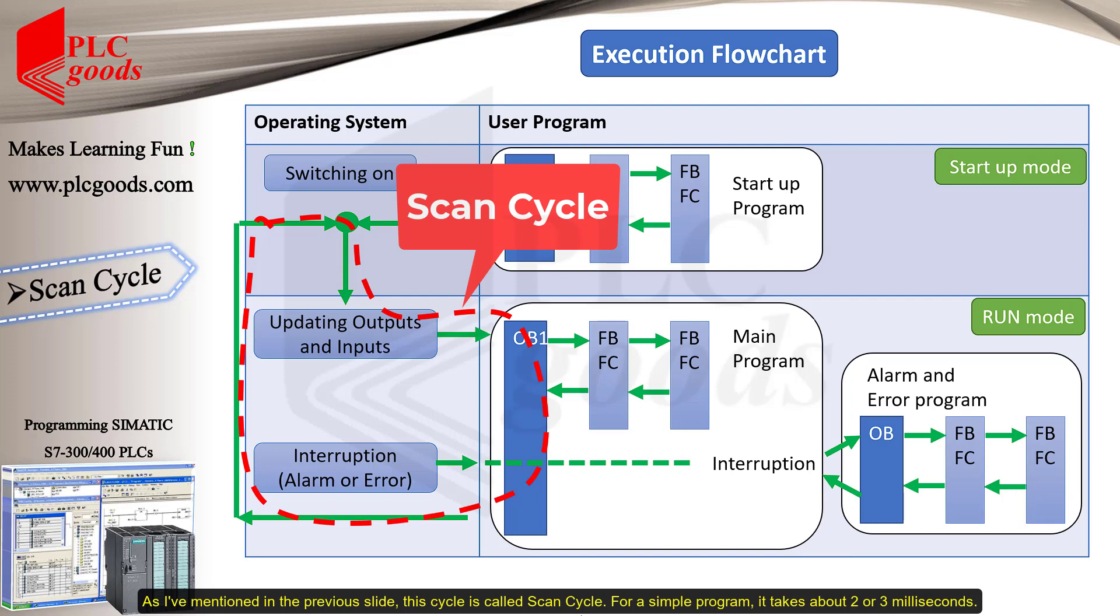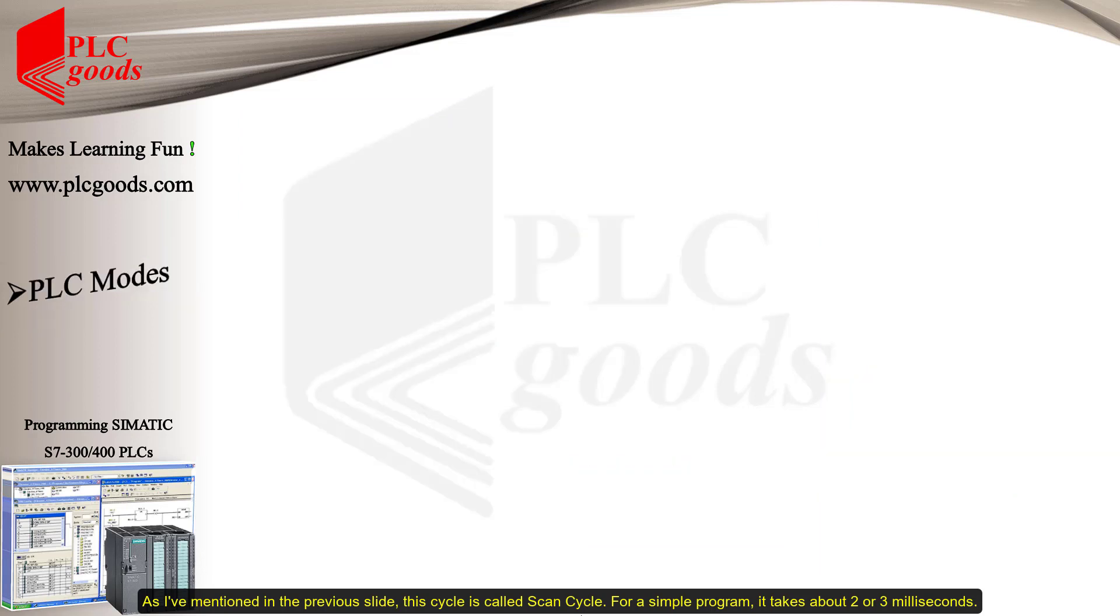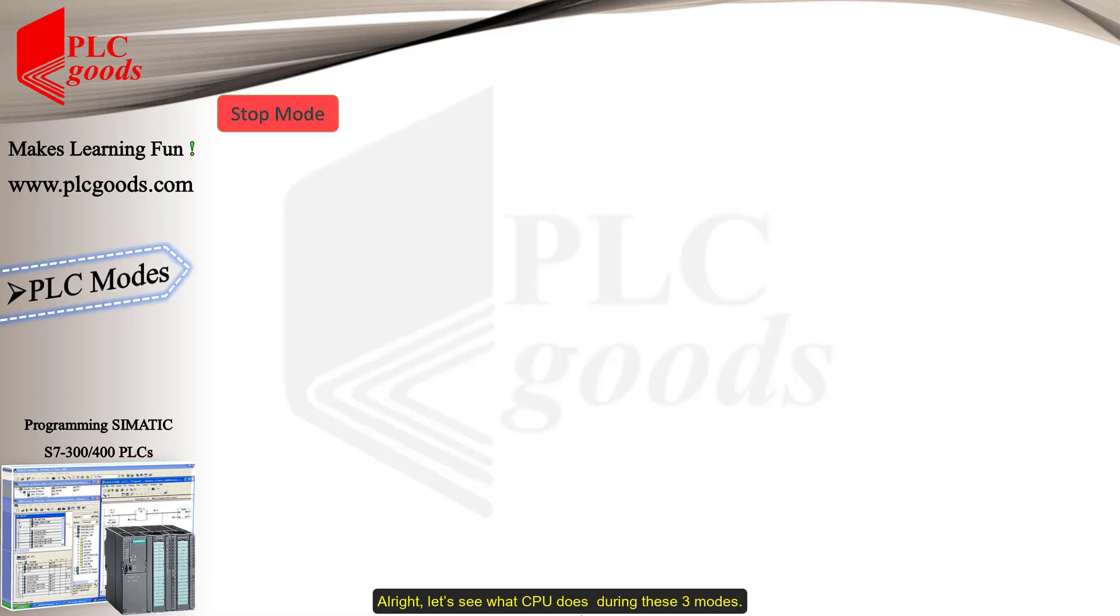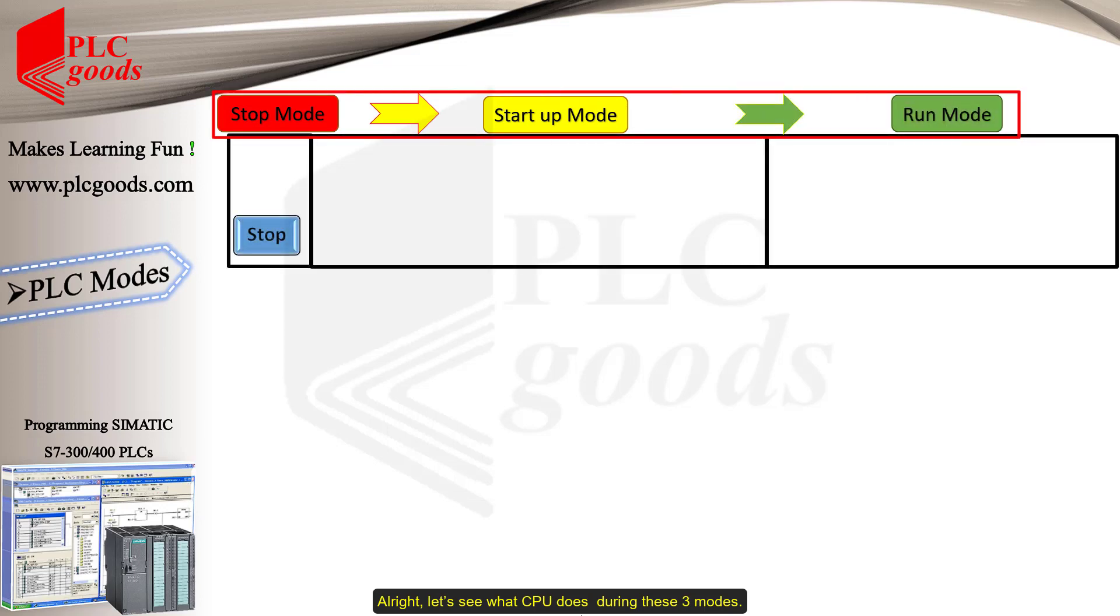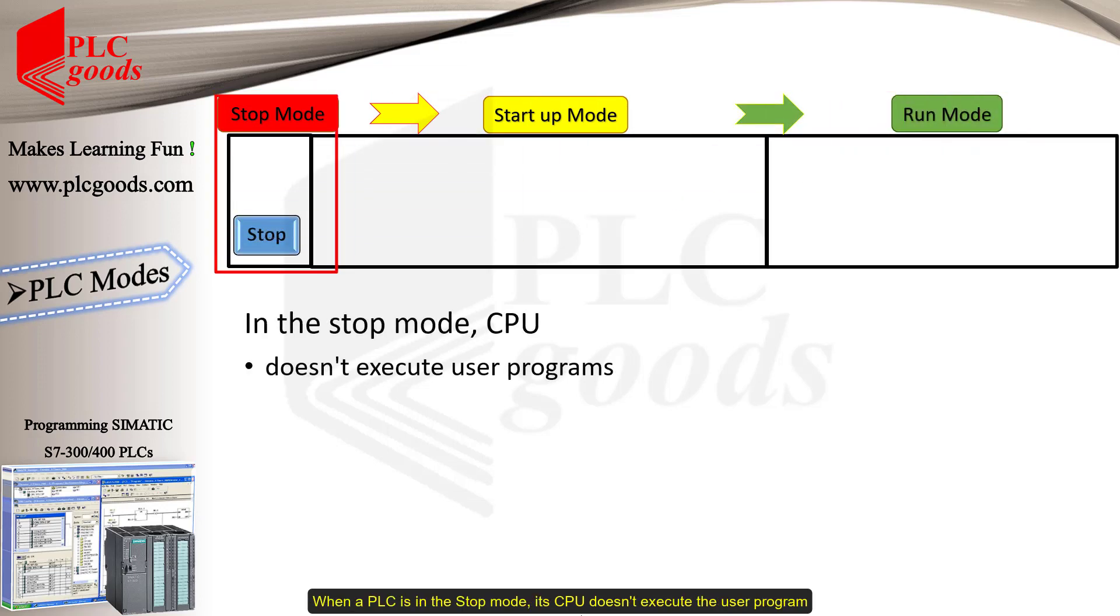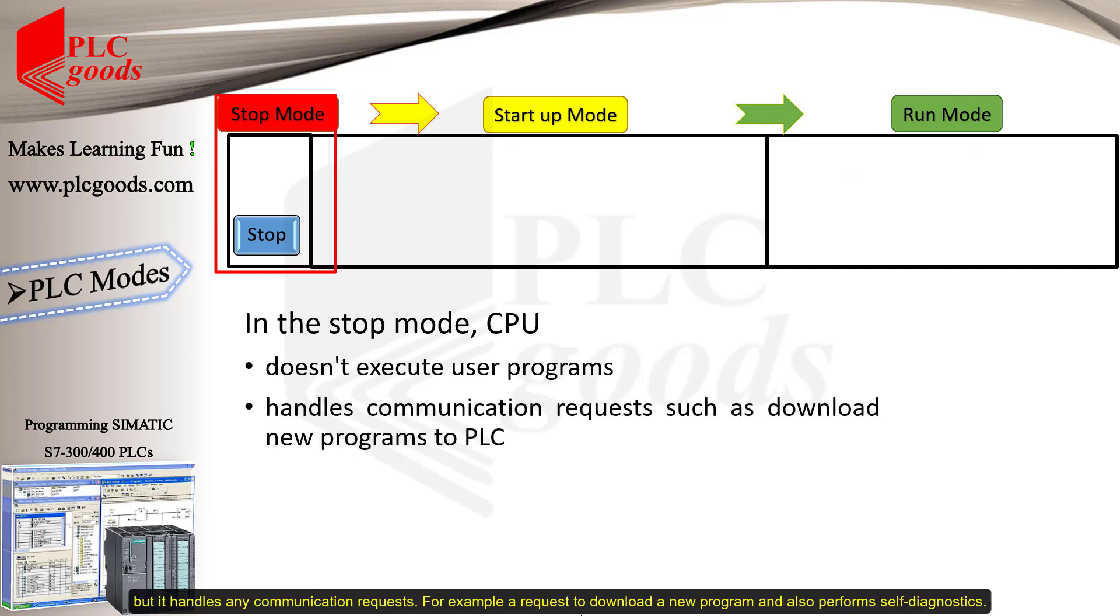For a simple program, it takes about 2 or 3 milliseconds. All right, let's see what CPU does during these three modes. When a PLC is in the stop mode, its CPU doesn't execute the user program. But, it handles any communication requests, for example, a request to download a new program, and also performs self-diagnostics.